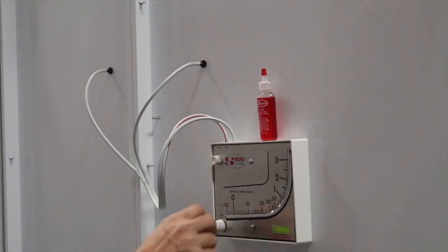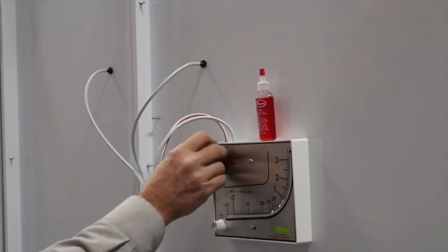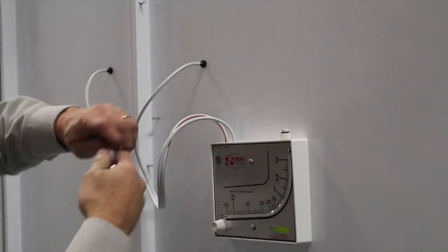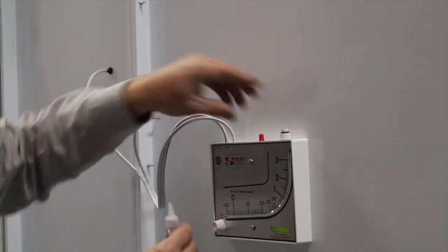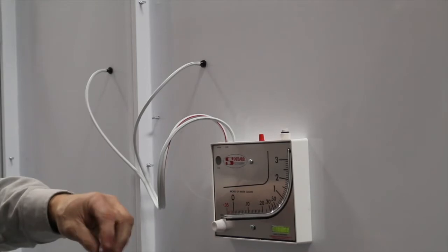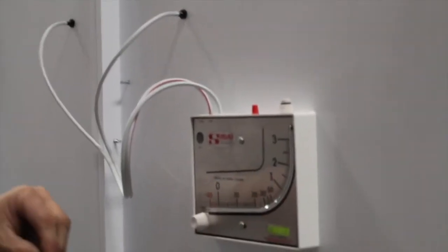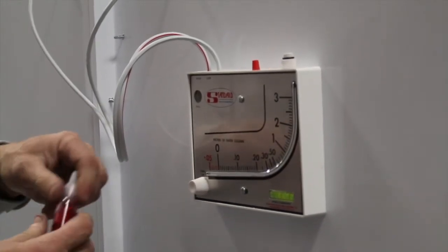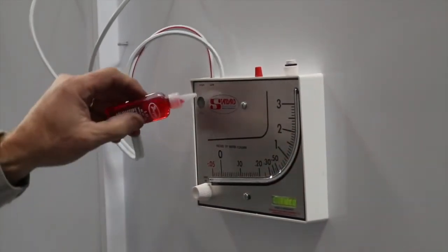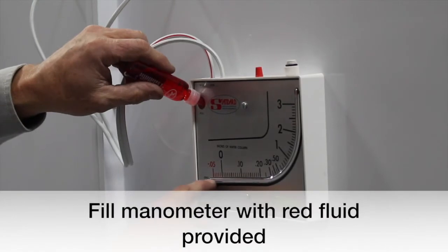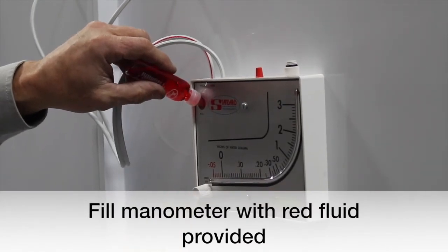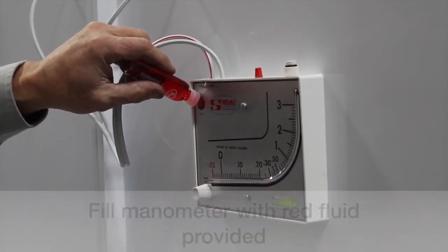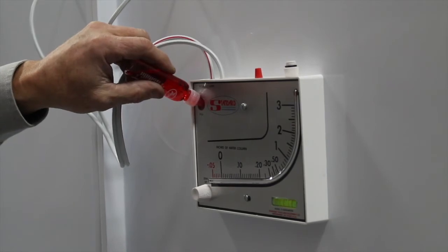Fill this with fluid. This is zero set, all the way into the right. Take that out. This fluid is a specific gravity fluid. It comes with the manometer. Take that piece out. Watch here for the red to start showing up, because you won't use the whole bottle.